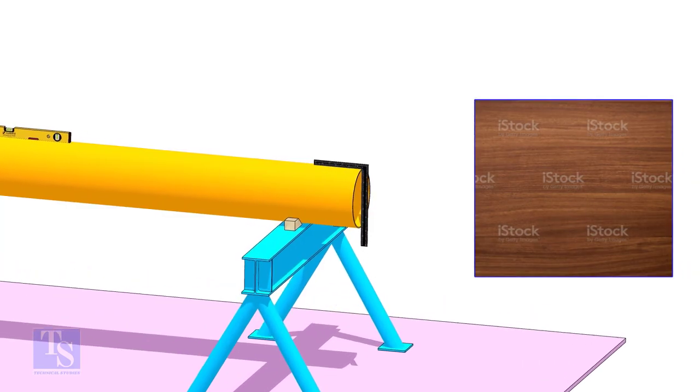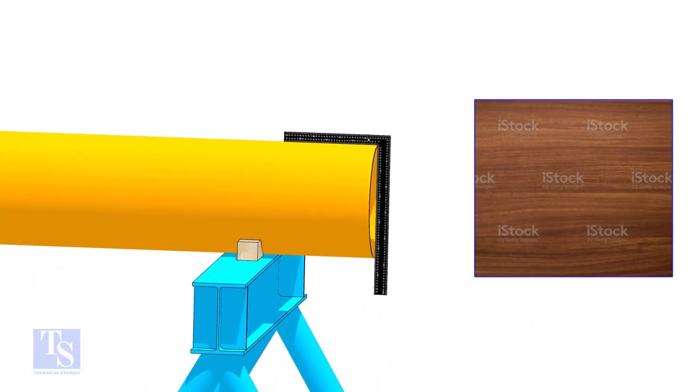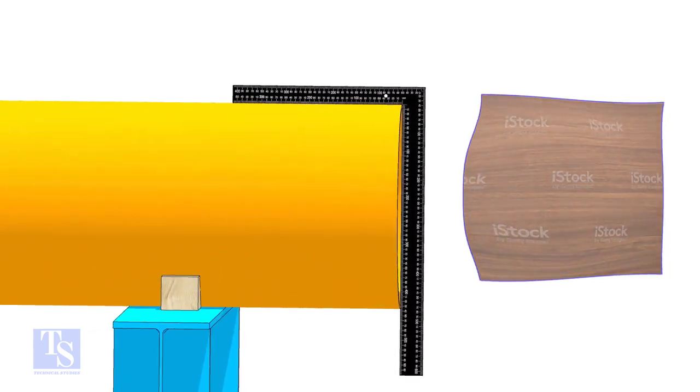To solve this issue, I use a 16mm thick, square-shaped, good quality plywood, 200-300mm larger than the diameter of the pipe.